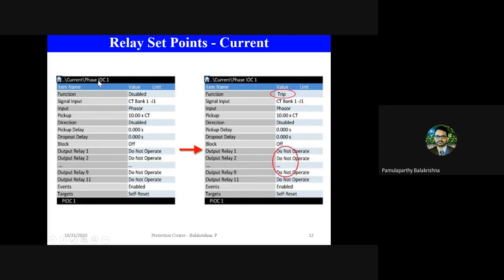Then this instantaneous overcurrent, on which signal? As I told, there is a hardware input coming to the relay, right? So it has to know which hardware signal it has to take. So that I have mapped here. The signal input for this function is CT bank 1 J1. This is the slot or the backside relay terminal I showed, from where the signal is connected. So I need to select that particular signal input. Second, I need to define whether I do this overcurrent protection on the phasor of the current or the RMS quantity of the current. So I can choose which form of computed current value I need to take for protection purposes. That is defined here, which is a computed quantity from the CT signal.